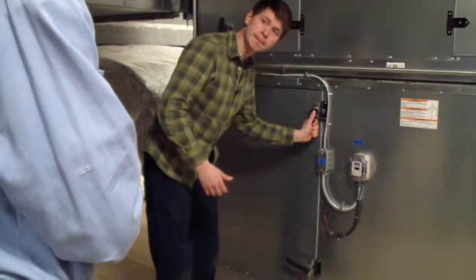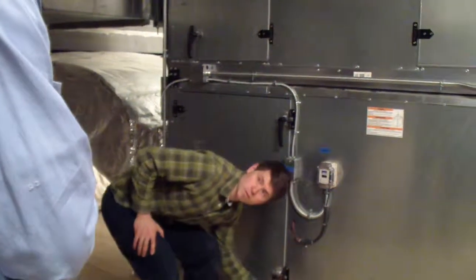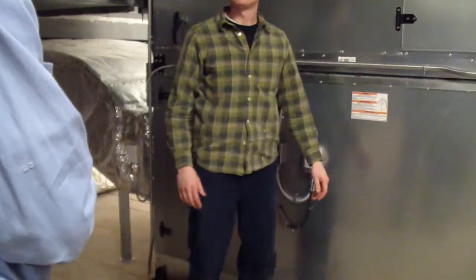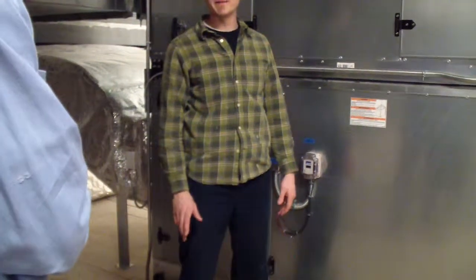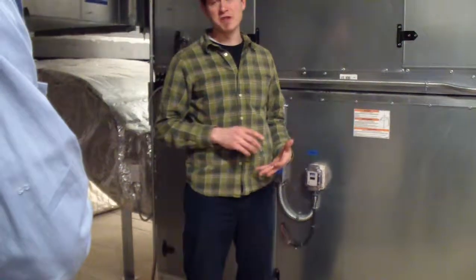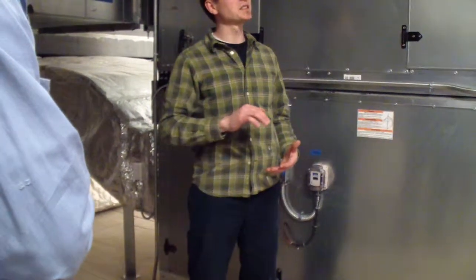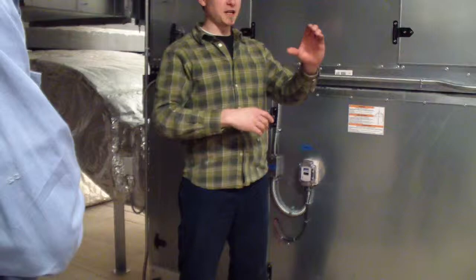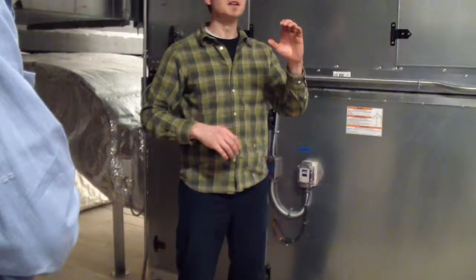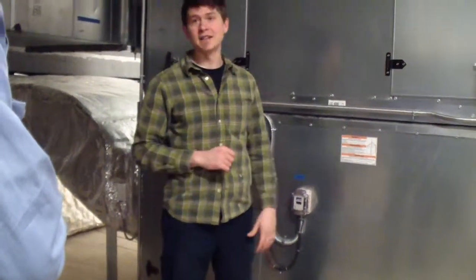Is that freeze manual reset? No, nope. So you can do that from the central, as we call it? Yeah, so it's an automatic reset, but it does need to be reset through software. So you will actually physically have to go into the software, and as I showed you, the button on the graphics page, hit that, and you can reset it.